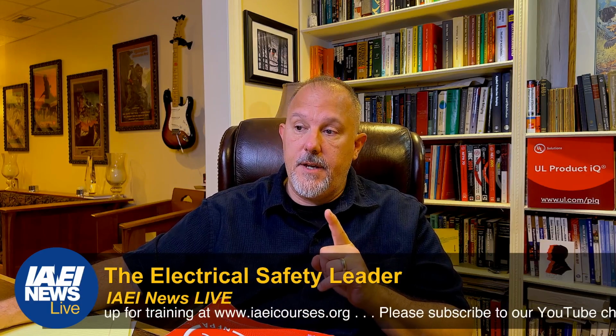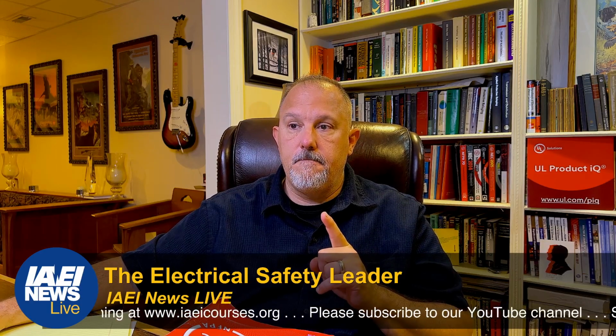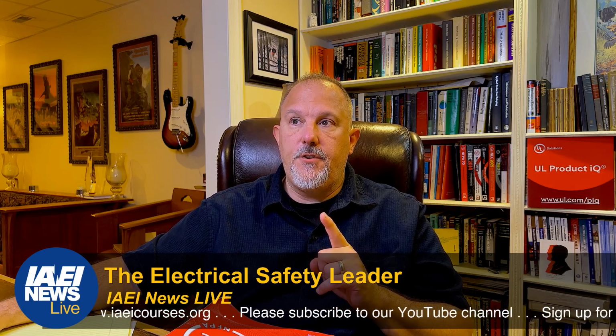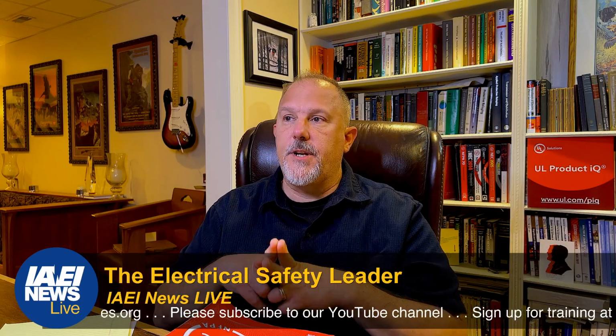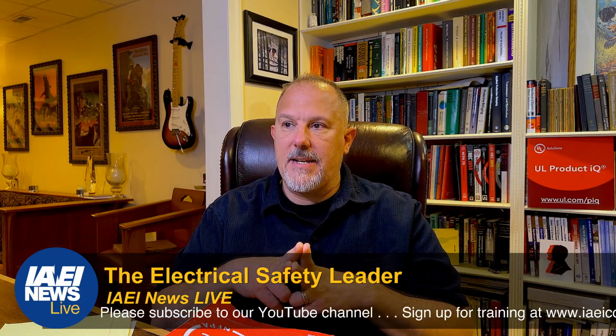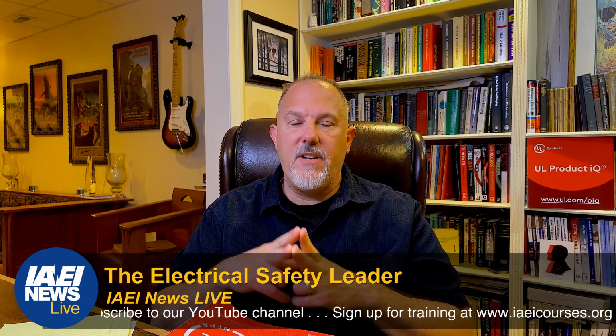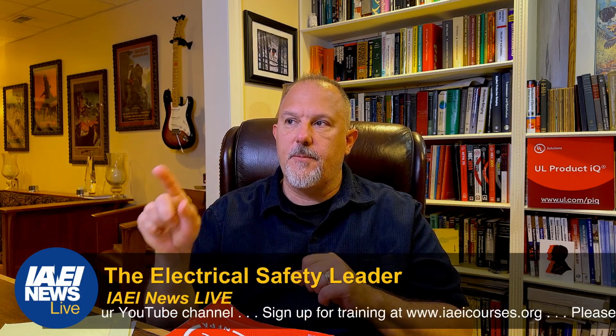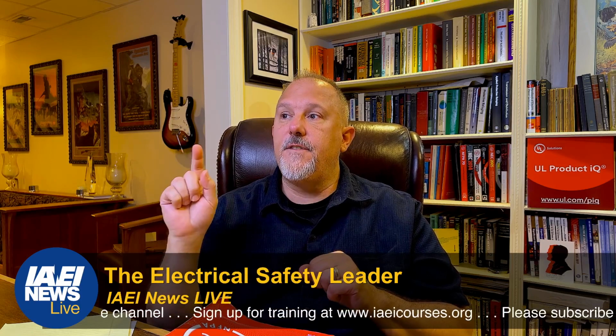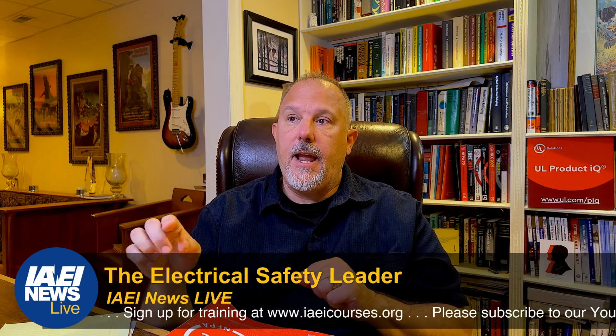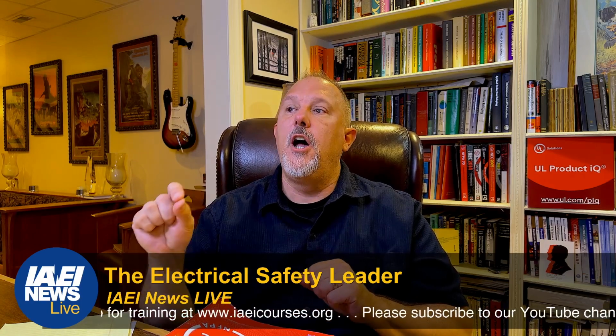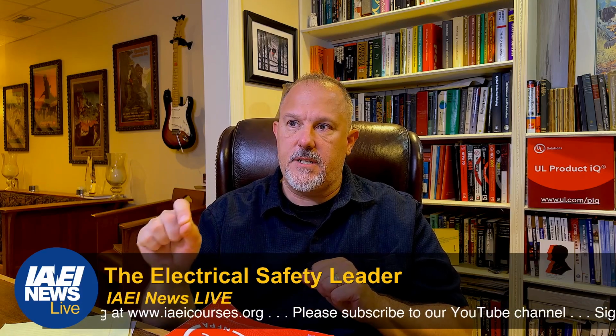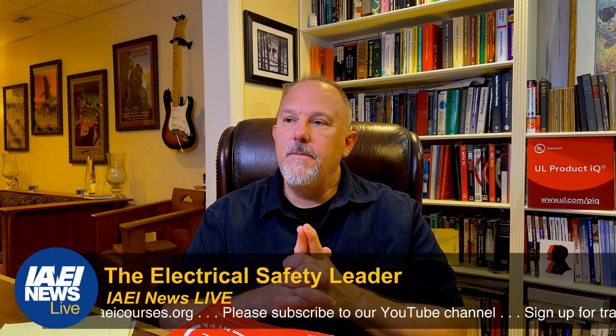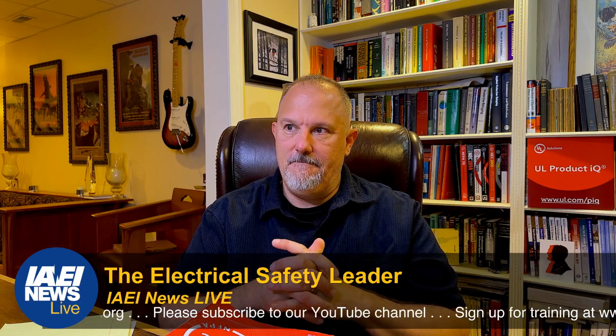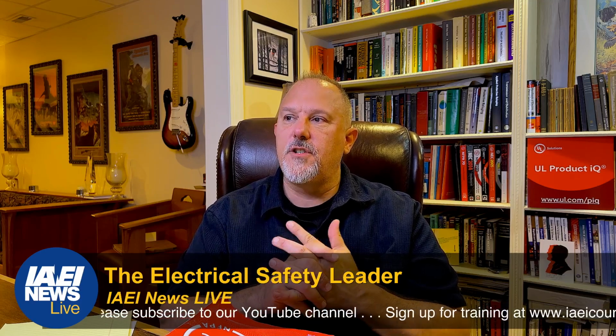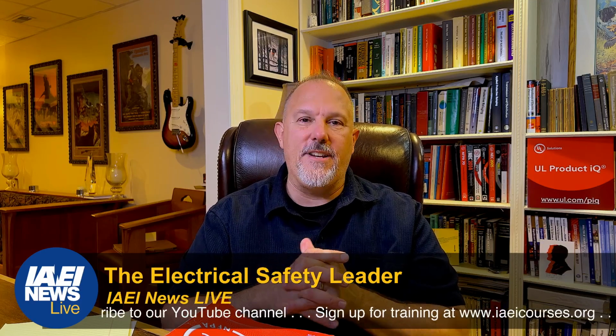Let's do this. Surge arrestor rating. In 242, surge arrestor rating, the duty cycle rating of a surge arrestor shall not be less than 125% of the maximum continuous operating voltage available at the point of application. For solidly grounded systems, the maximum continuous operating voltage shall be the phase to ground voltage of the system. And it says for impedance or ungrounded systems, the maximum continuous operating voltage shall be the phase to phase voltage of the system. There's an informational note. Here we go. IEEE C62.11. Standard for metal oxide surge arresters for alternating current power circuits greater than 1 kV.